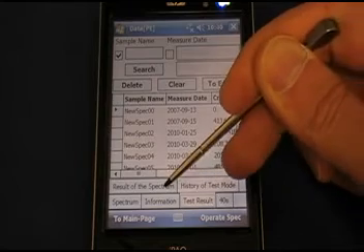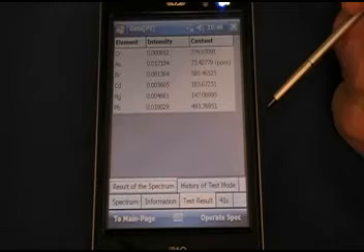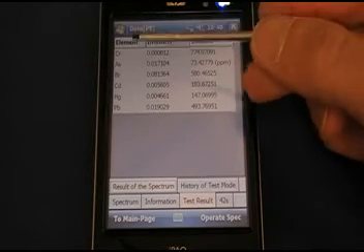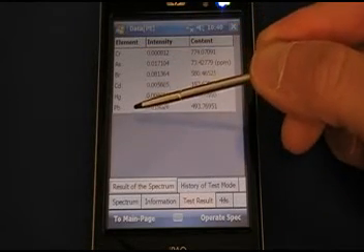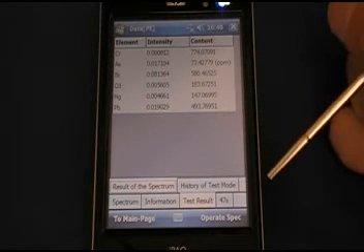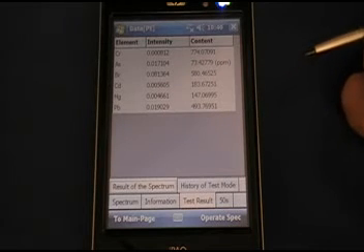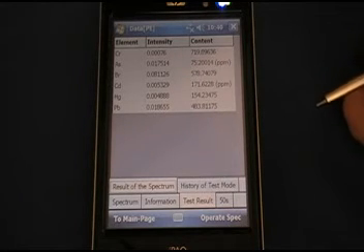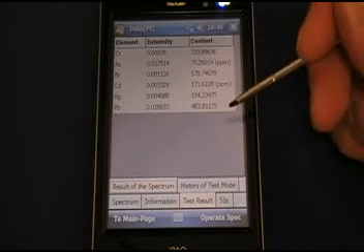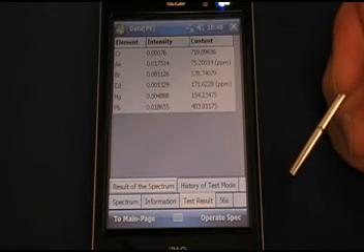And we want to go to the result of the spectrum, and we see the results coming in. This is set up for the major elements in the ROHS applications, also helpful in CPSIA. That is a brief example of how this system can get you some accurate results on hazardous substances. And as we're winding down here, we see the lead content sitting about 480. The sample piece itself is right in that range.